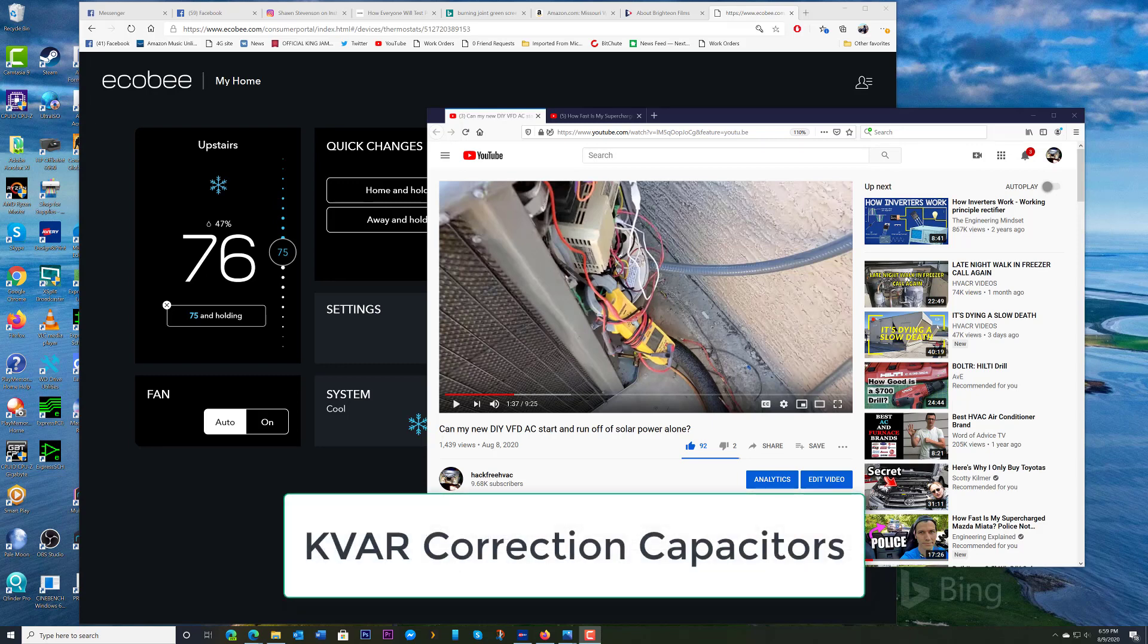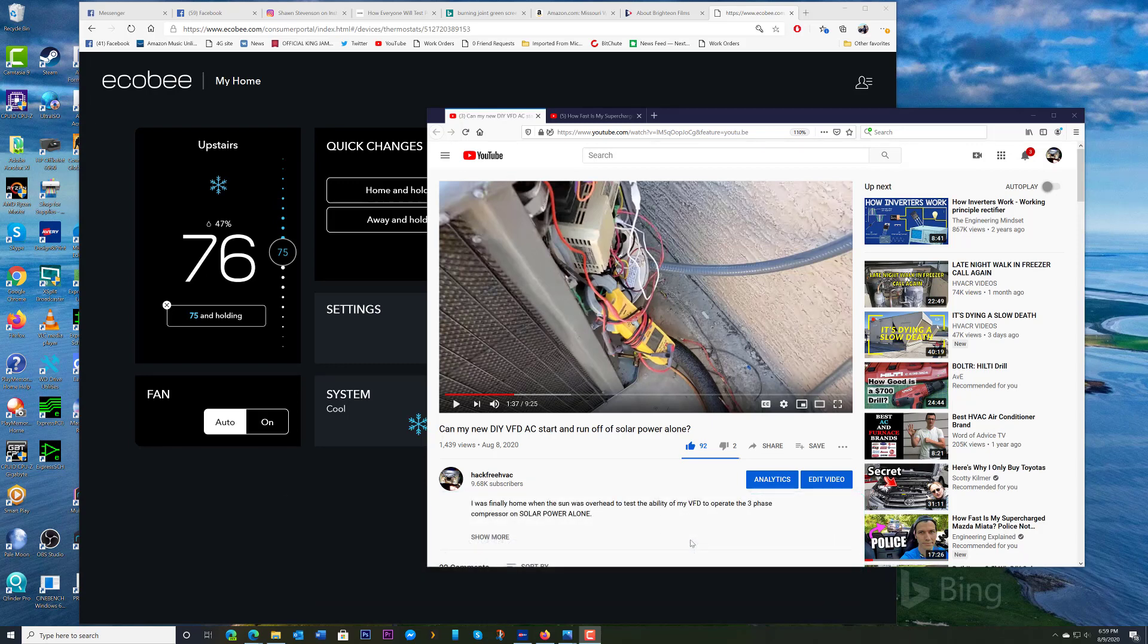With the capacitors it actually just goes back and charges the capacitors right there locally at the motor. And actually your power you read on your line side coming from your utility goes down when you have those power factor capacitors. That is if your power factor was way off, usually from a larger motor when it's needed.